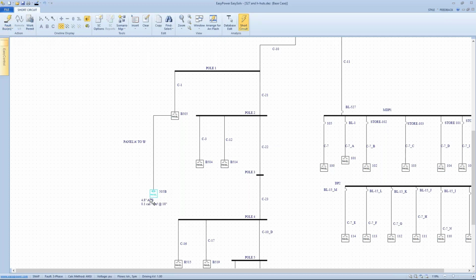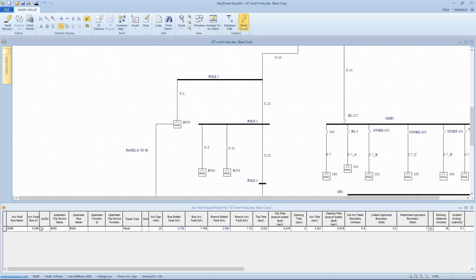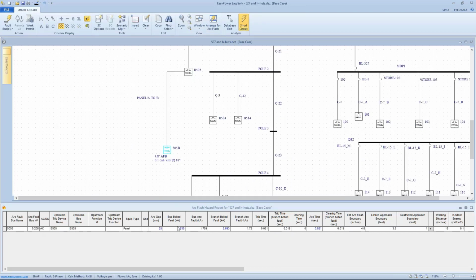And what we see, and this is what you want to do in any case, is the next step is to go to arrange for arc flash, and the tool shows me what it's using for calculations. Here in this particular case, we have a fault current at this particular panel of 2,755 amps. Again, this is a three-phase number, of which the maximum arcing current would be 1,700 amps. At that point, the tripping device is the B505 circuit that we set up here. Because we set up those independent settings, we're in pretty good shape.